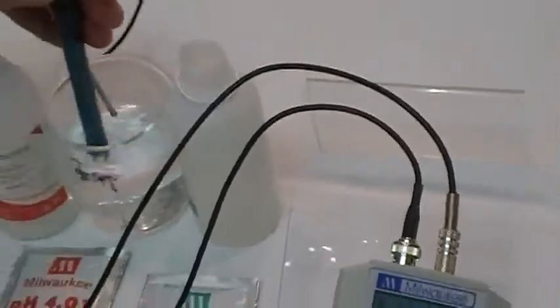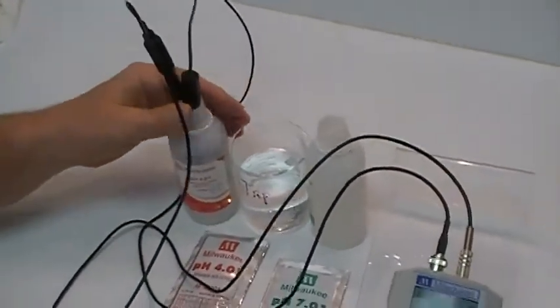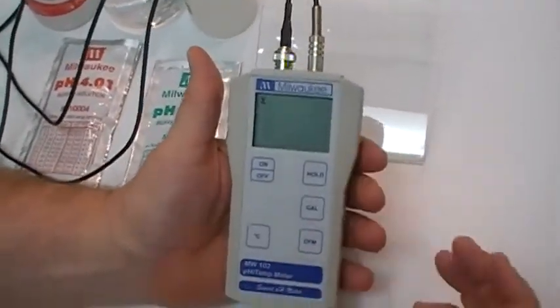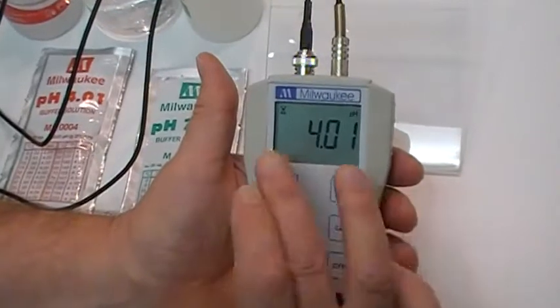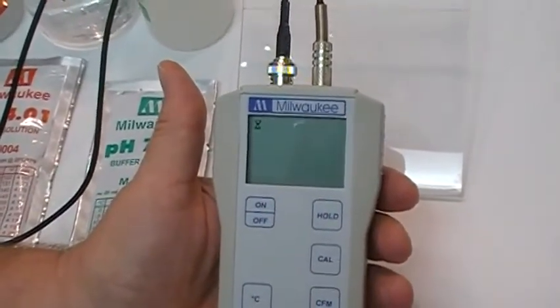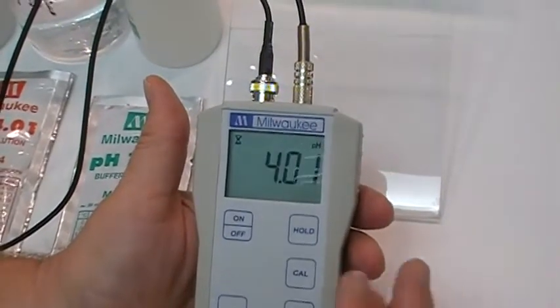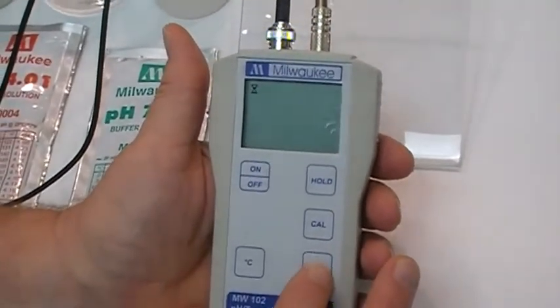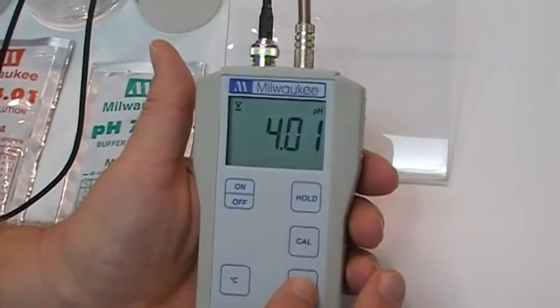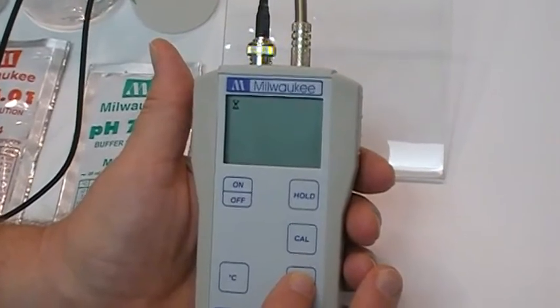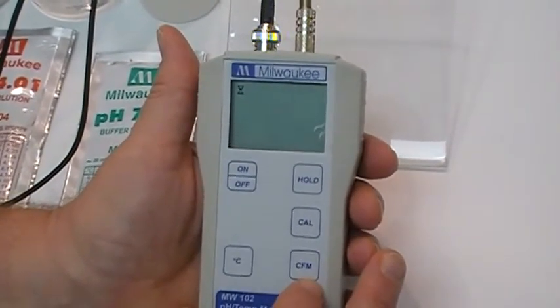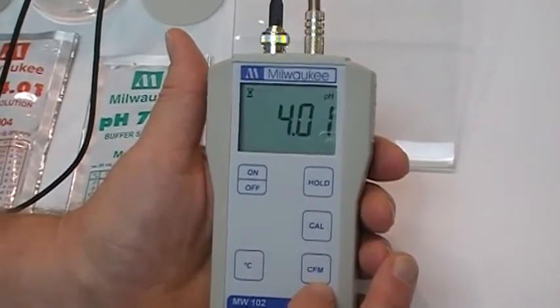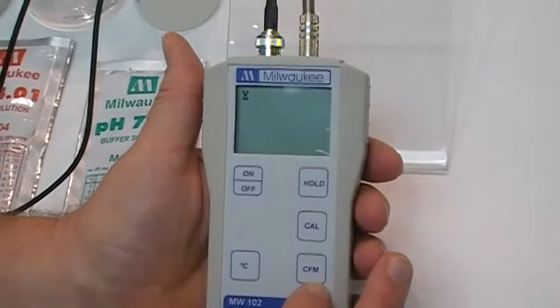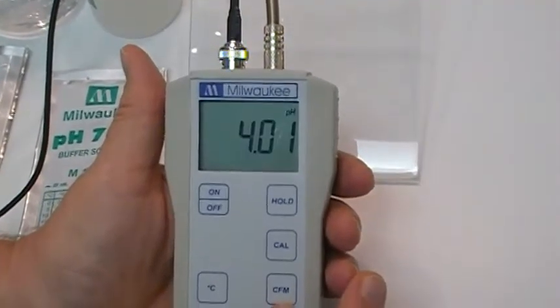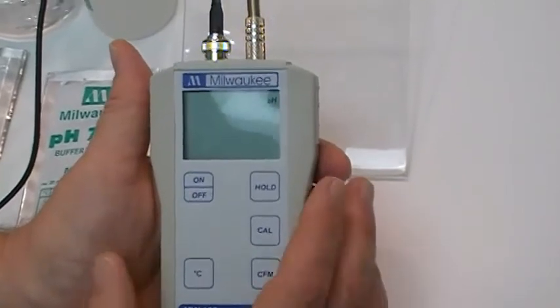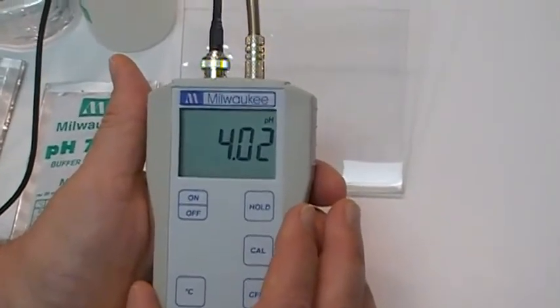You can do a rinse and then over into the 4 calibration solution. And now you see the pH is blinking again with the 4 blinking. Hourglass is showing in the left side, meaning it's functioning. And when it stops blinking, you hit the CFM. And 4 usually takes longer than the 7 does to hit the mark because the probe needs to come down to the 4 position. There's your CFM. And as you see, it comes in.